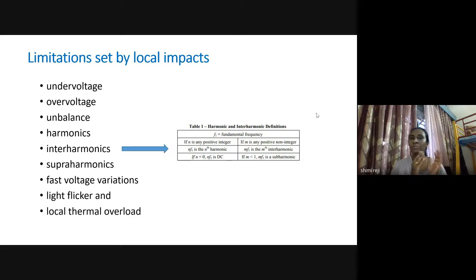For lower order harmonics, we go up to 2 kilohertz, and higher order harmonics start from 150 kilohertz and above. IEEE and IEC had never given standards between 2 kilohertz and 150 kilohertz, because before, when power electronics came, the switching frequency was mostly in the lower or higher order, not in this range. But now many manufacturers, and in power line communication, this range was used, so some standards were defined for those periods.